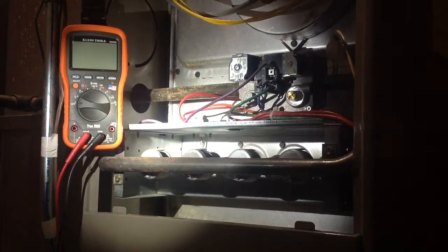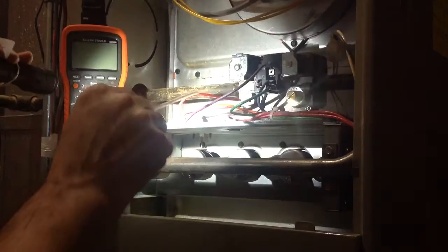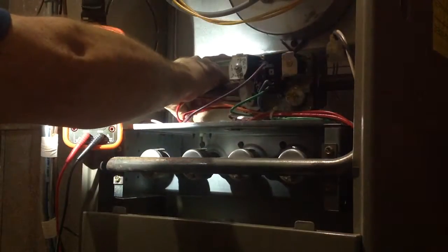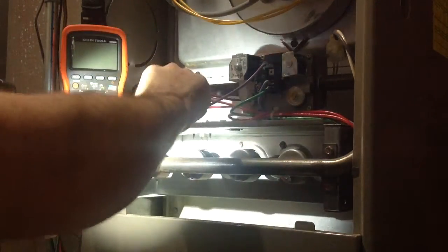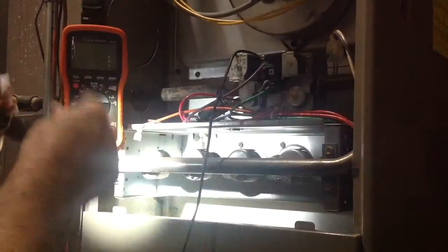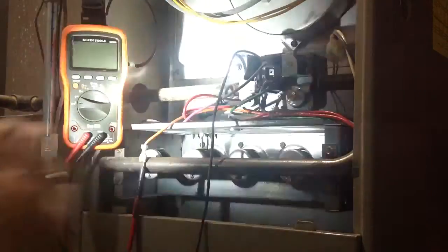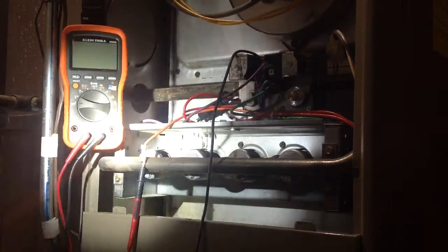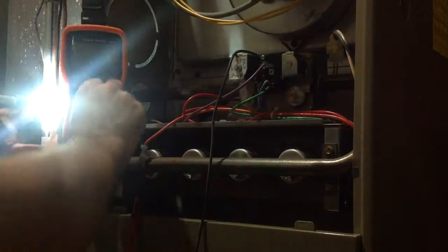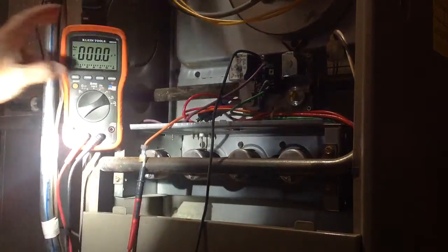So the way we measure microamps is, you notice that this probe here comes up to a wire which goes to the sensor. So we have to put our meter in series with that wire. So we disconnect that from the tab. Let's clip on our negative probe there. Put our positive probe inside this terminal lug. We've got our meter set to the microamp, the test probes plugged into microamps. So we'll turn on microamps here, select DC current.